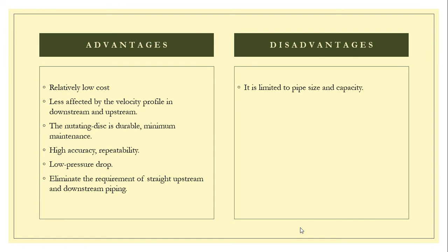Disadvantages: it is limited to pipe size and capacity because it's designed in small sizes. Only clean fluids can be measured, because unclean fluids that contain solid particles may affect its performance and decrease its efficiency. Lastly, accuracy is affected by the viscosity of fluid flowing through it. Since the disc nutation happens naturally, the accuracy of this type of flow meter can be adversely affected by fluctuations in liquid viscosity.